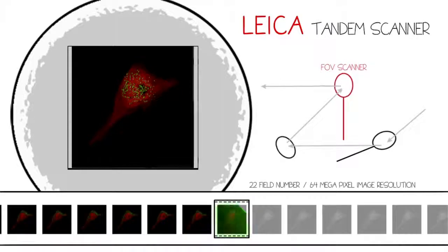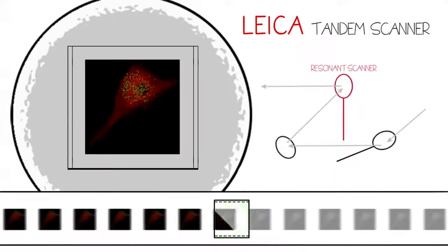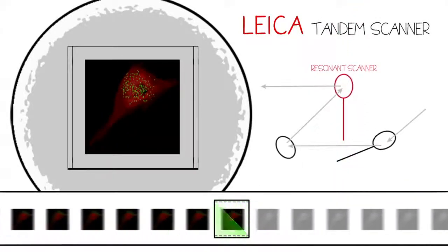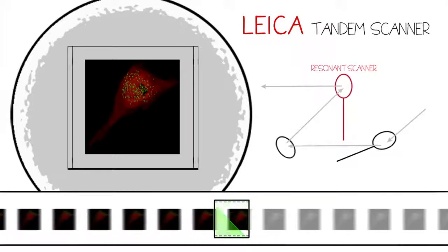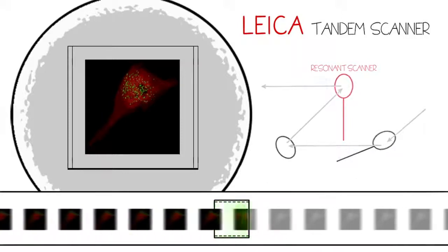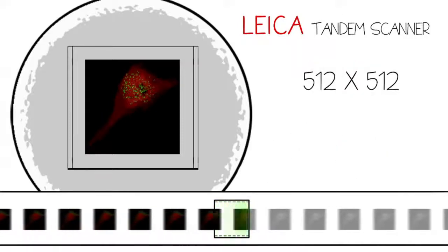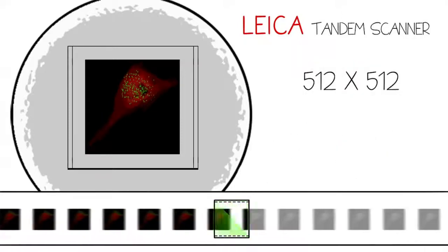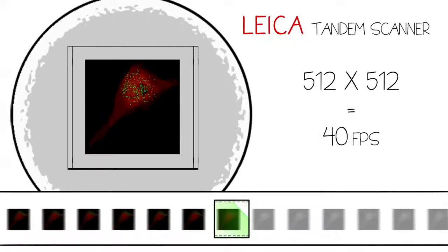Leica's fastest resonance scanner oscillates at 12,000 Hz in the x-direction and can run at a bidirectional rate of 24,000 lines per second. For a standard 512 x 512 live cell imaging resolution, this translates into 40 full frames per second.